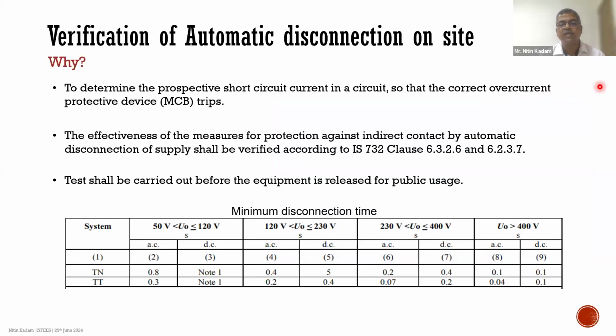Now, verification of automatic disconnection on site. Why is this required? As we said earlier, it is not just enough to have an MCB or an RCD connected in the circuit. You should have the right ratings of MCBs and the right values of RCDs connected, based on the rating of the prospective short circuit current, as well as the time that is required to trip. So before the equipment is handed over to the customer, we should verify that the protective devices are tripping according to the values that are specified for the fault loop current, as well as the minimum disconnection time that is specified in the code.